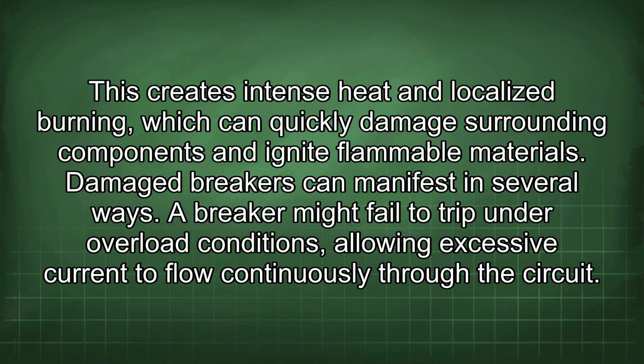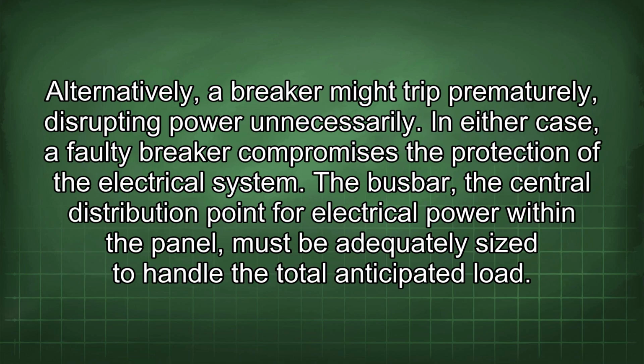Damaged breakers can manifest in several ways. A breaker might fail to trip under overload conditions, allowing excessive current to flow continuously through the circuit. Alternatively, a breaker might trip prematurely, disrupting power unnecessarily. In either case, a faulty breaker compromises the protection of the electrical system.